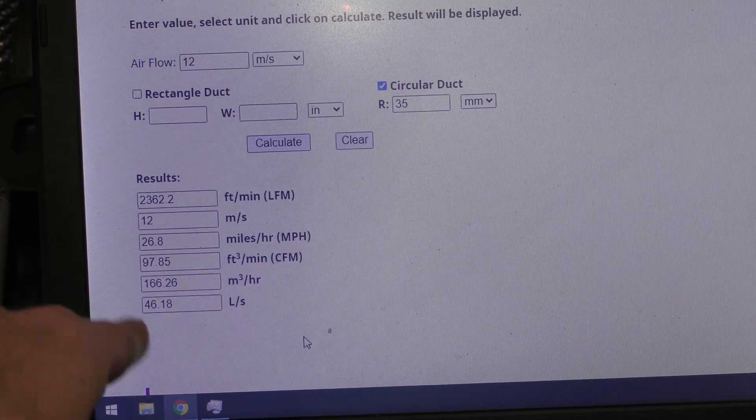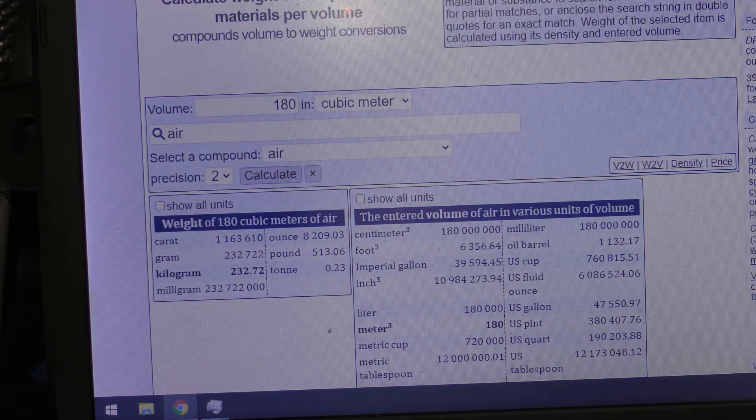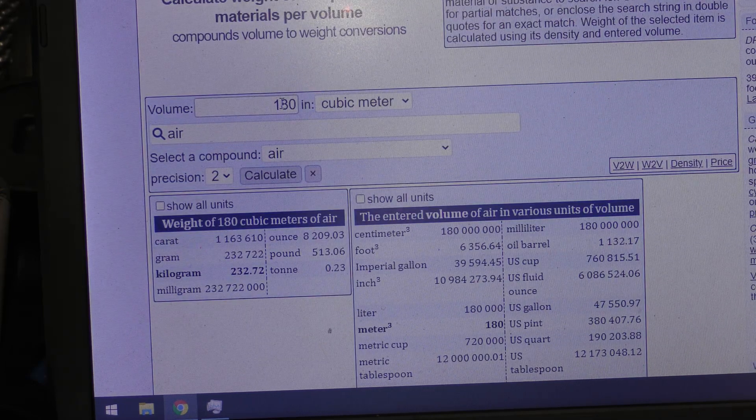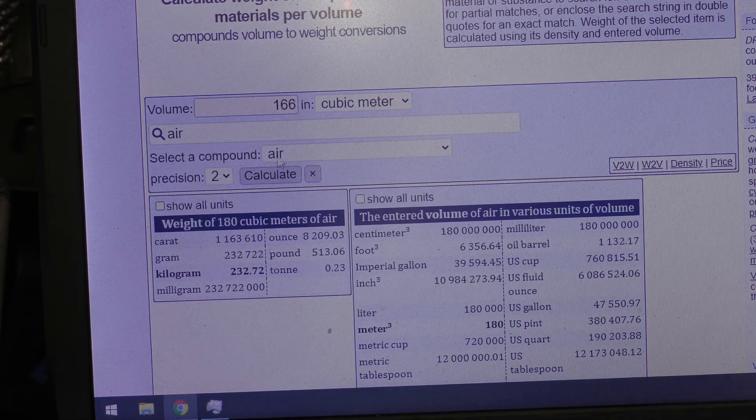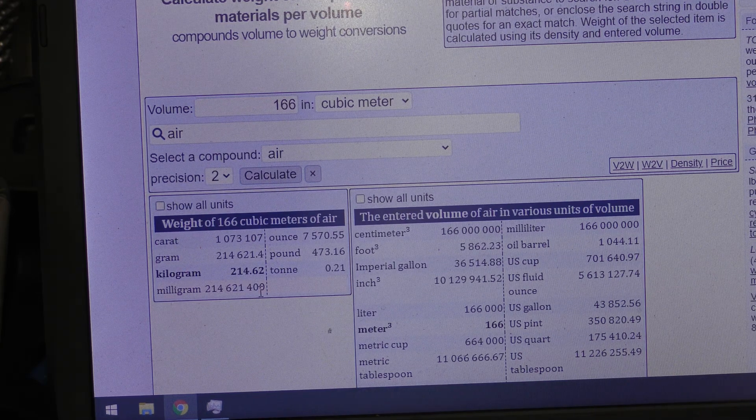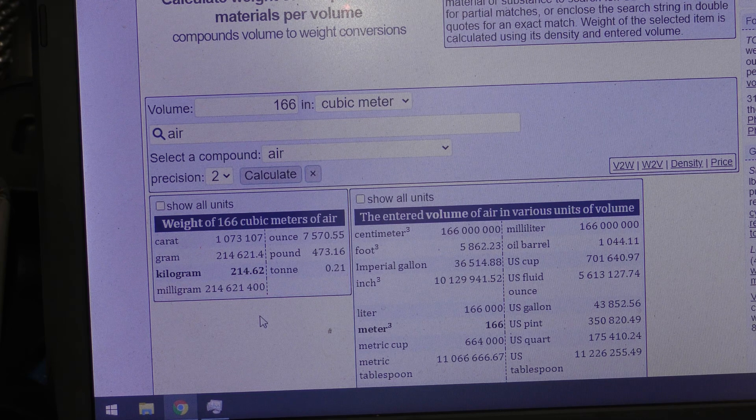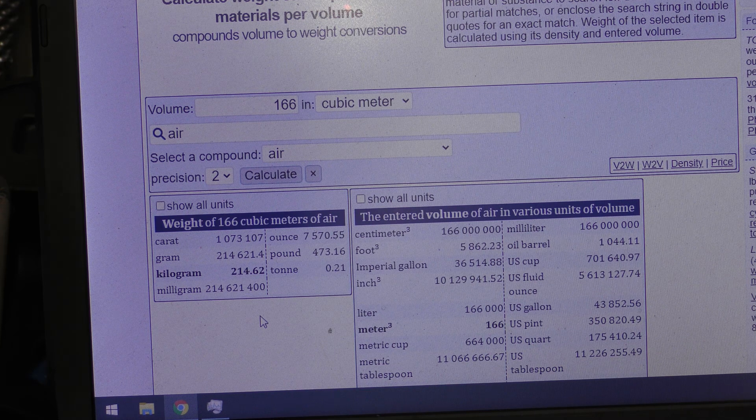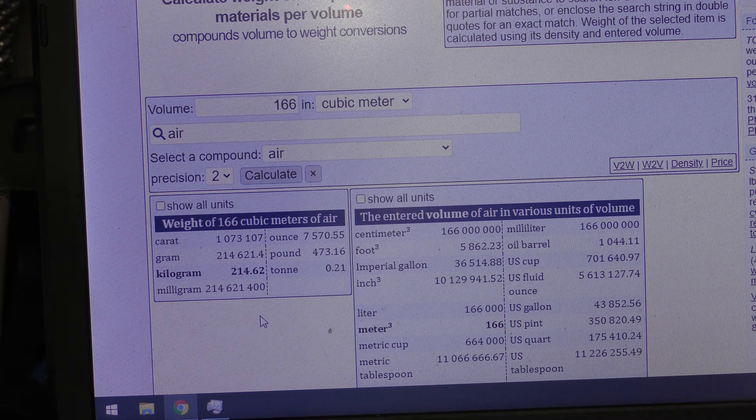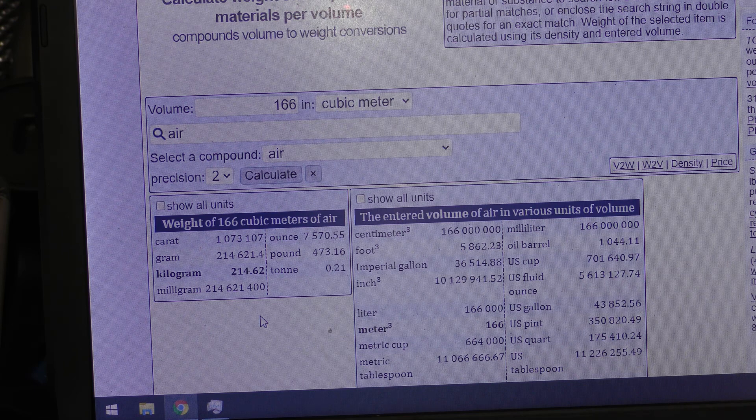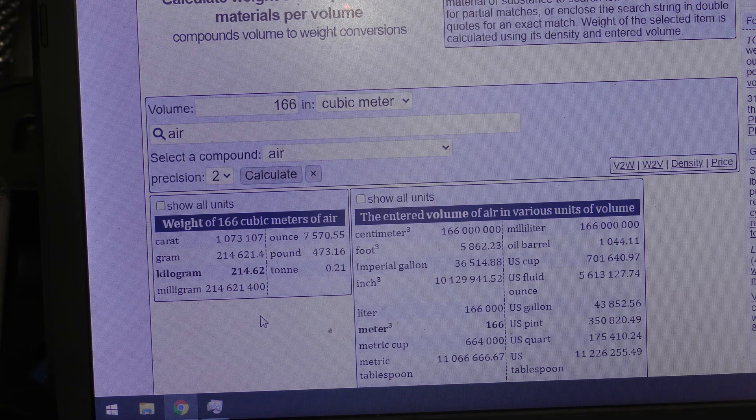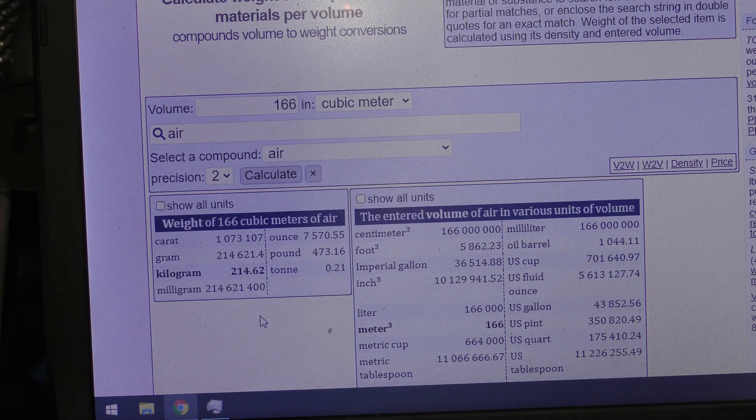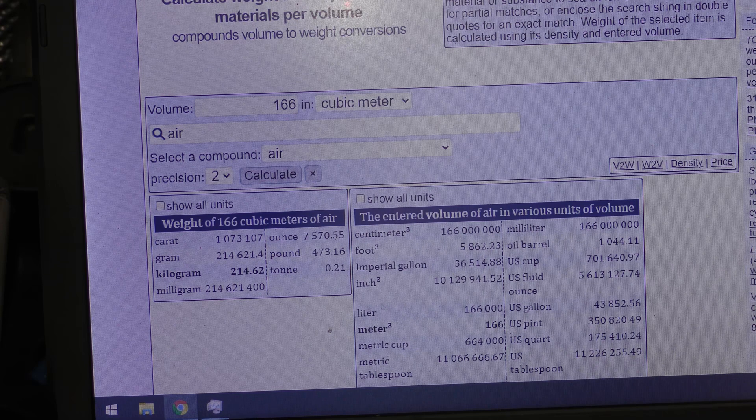166 cubic meters of air is 214.62 kilograms of air per hour. So let's just make it 215 kilograms, 215 kilograms of air per hour. Now we'll move on to the temperature calculations.